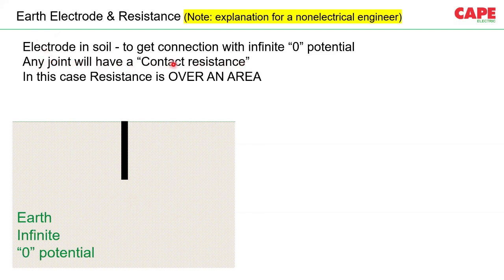Now, any joint will create a contact resistance. You know very well, even if you terminate two wires, of course there will always be a contact resistance. Whenever you make a joint, of course there will be a contact resistance. In case of this contact, that means the contact from a wire to the earth, it is over an area. In a normal contact, you can see the contact and the resistance is within this particular contact area. Whereas in case of an earth, this resistance is over an area.